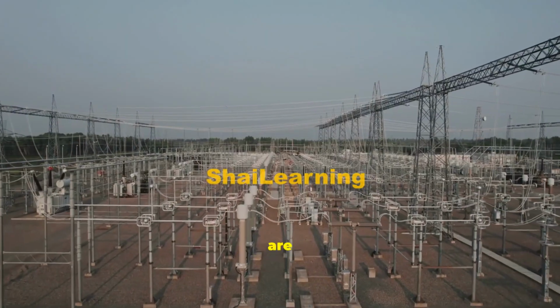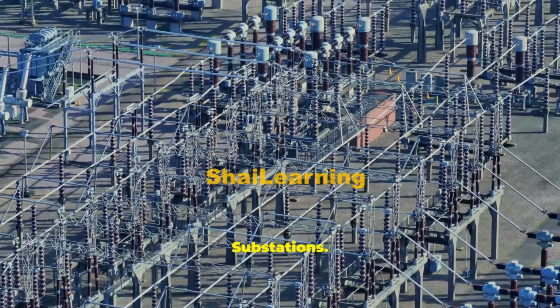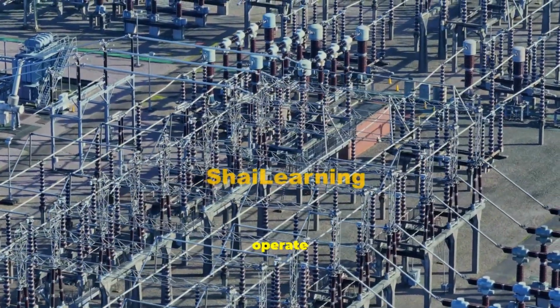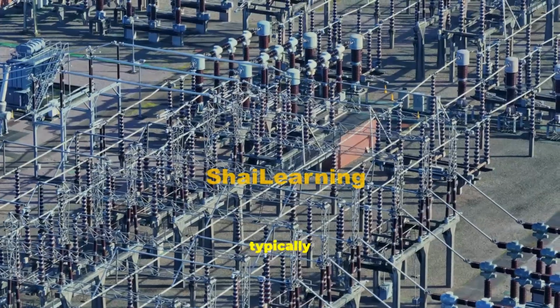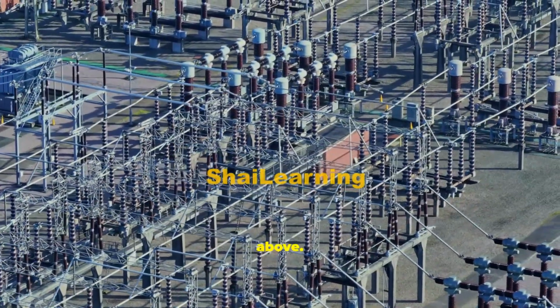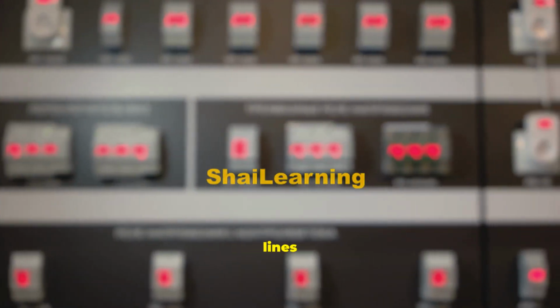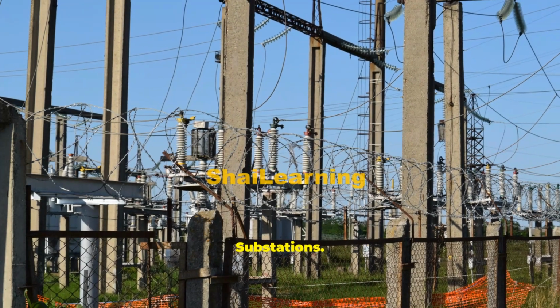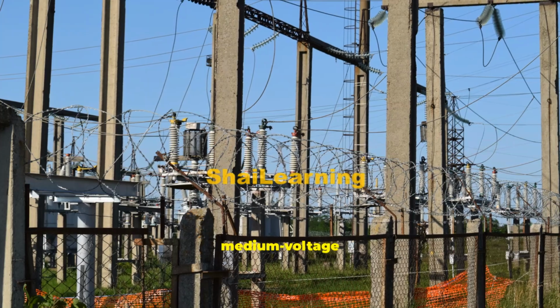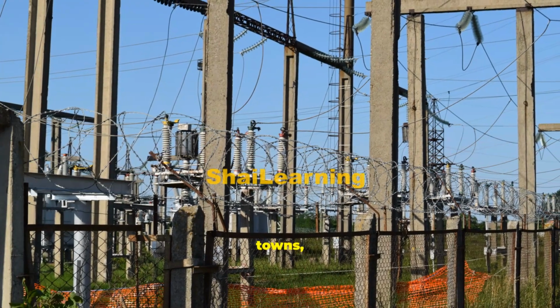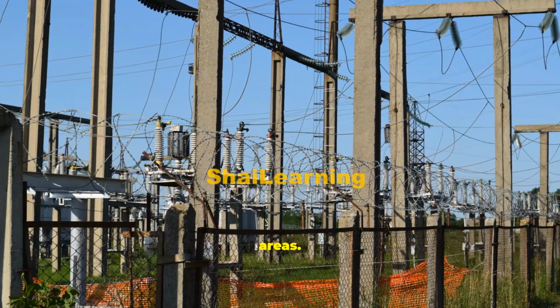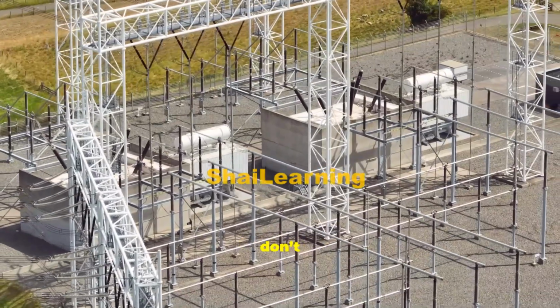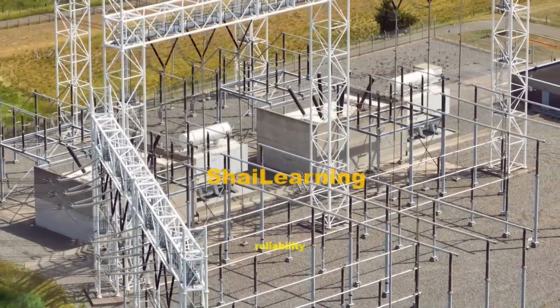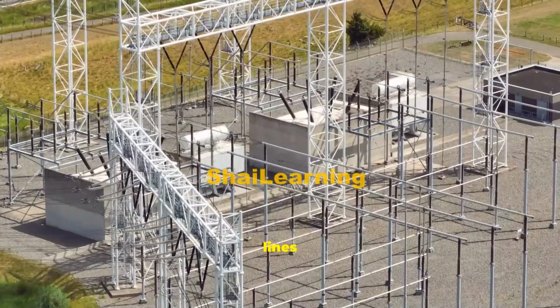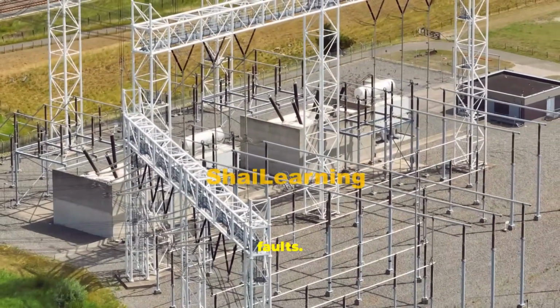Not all substations are the same. Transmission substations. These operate at the highest voltage levels, typically 115 kilovolts and above. They connect transmission lines and often support regional power flow. Distribution substations. These step voltage down to medium voltage levels and supply cities, towns, and industrial areas. Switching substations. These don't change voltage. Their job is reliability, switching lines in and out during maintenance or faults.